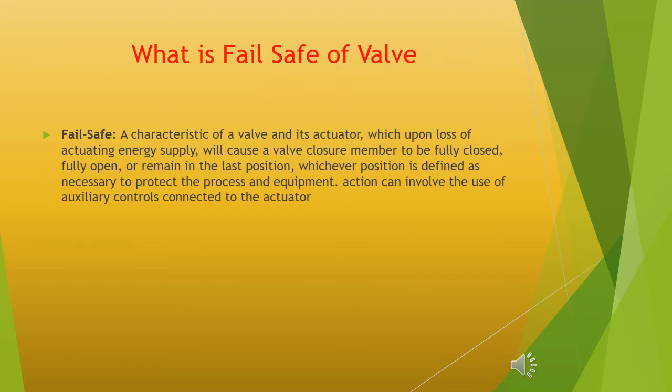What is fail safe of a valve? Fail safe is a characteristic of a valve and its actuator which, upon loss of actuating energy supply, will cause a valve closure member to be fully closed, fully open, or remain in the last position — whichever position is defined as necessary to protect the process and equipment. This action can involve the use of auxiliary controls connected to the actuator.